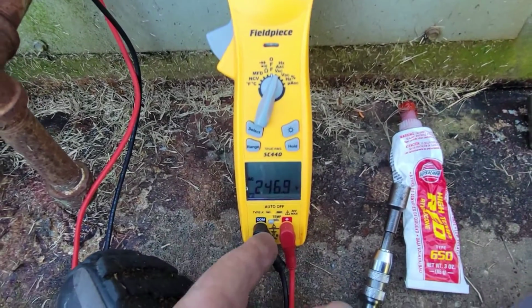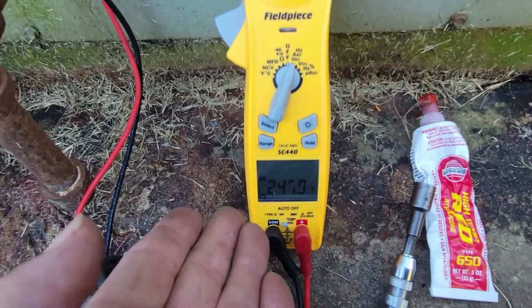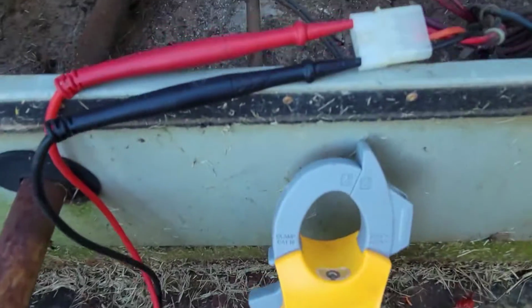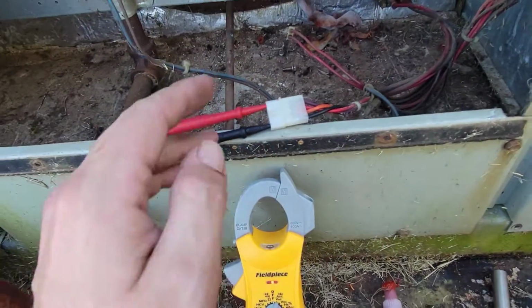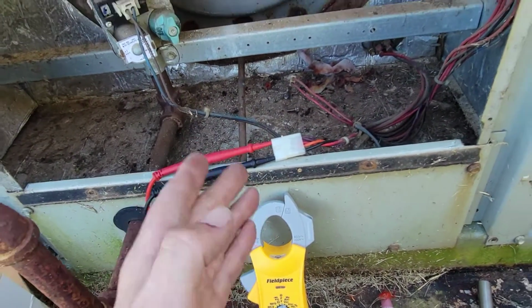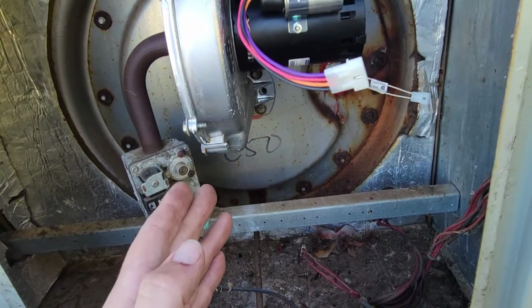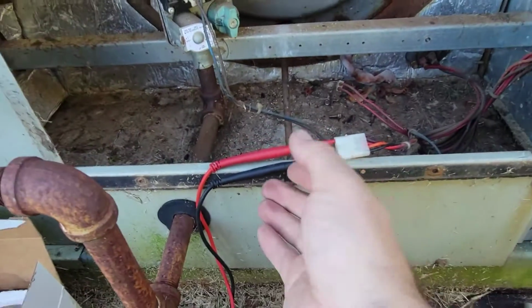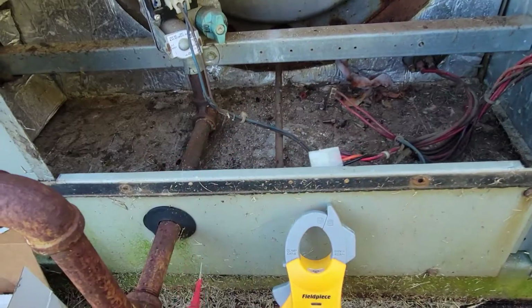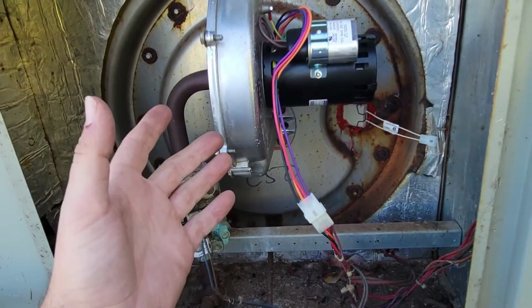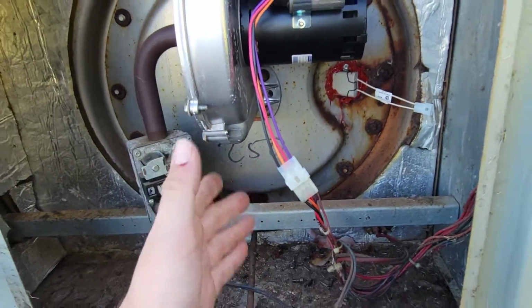What comes first? All right, so we got a call for heat. First thing that should happen is our inducer assembly should come on. And we've got 247 volts coming out of the plug that comes from the board and goes to the inducer assembly. So now that we know we have voltage, we should plug it in and see if it works. You can hear the motor running that's plugged in. I'm going to plug it into the old motor and show you what it was doing.